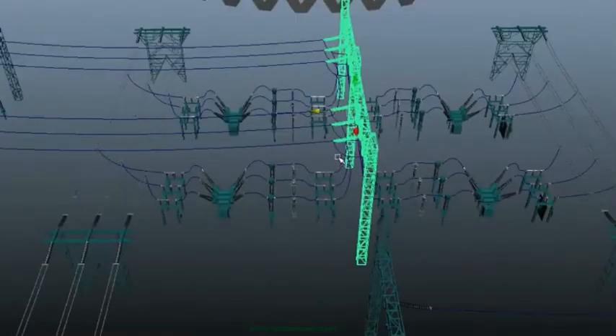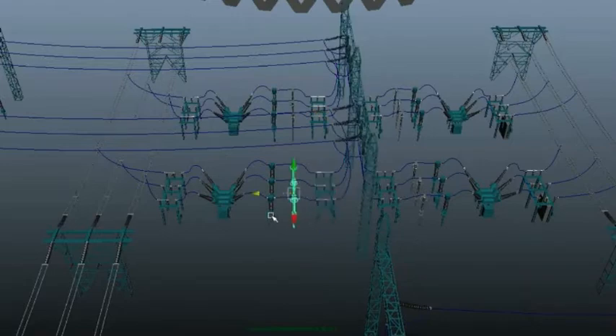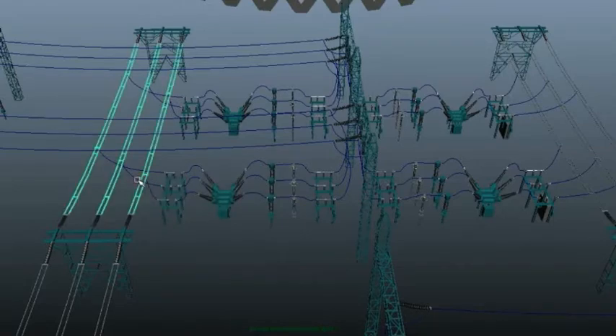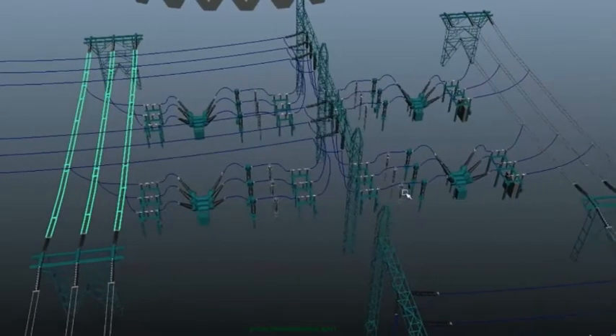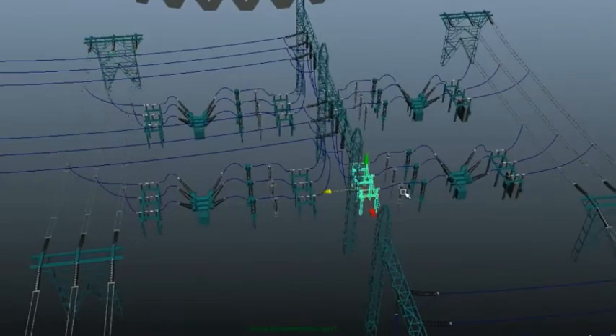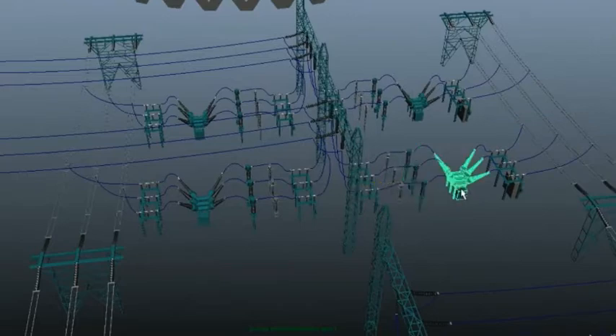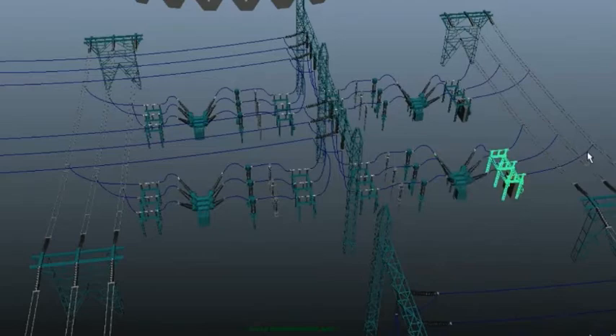From this, after the gantry, the supply will go to both the buses. For this, the conductors will go down, then go through the isolator. After this, a surge arrestor is installed, then the current transformer to measure how much current is going on this bus. Then circuit breaker, then isolator, and then finally these conductors are connected to bus 1. Similarly, the connection also goes to bus 2 and follows exactly the same sequence. First isolator, then surge arrestor, current transformer, circuit breaker, isolator, and finally it will be connected to bus number 2.